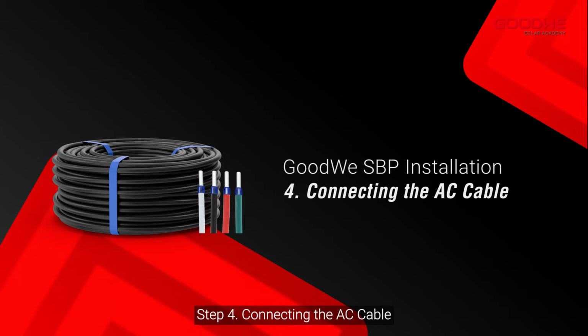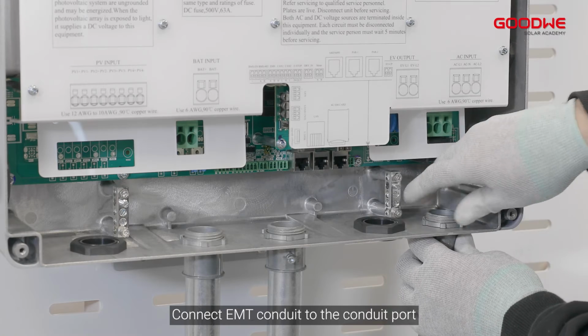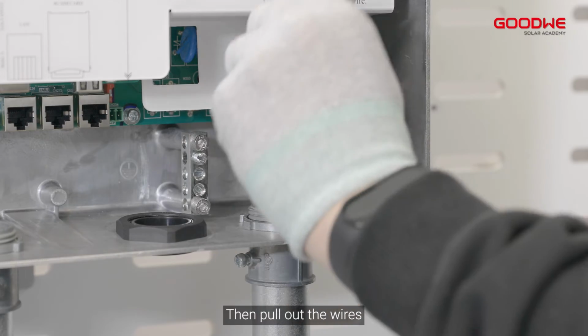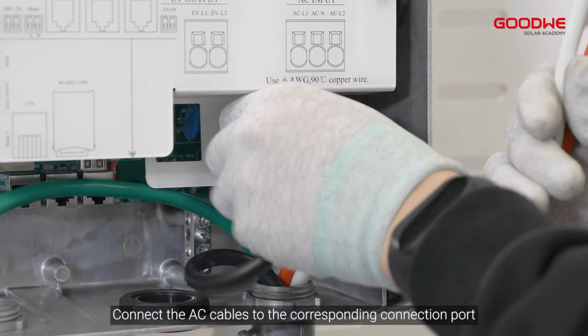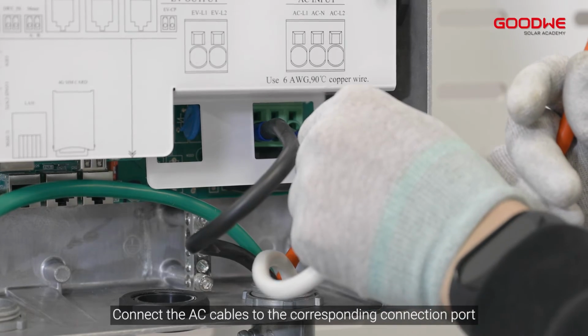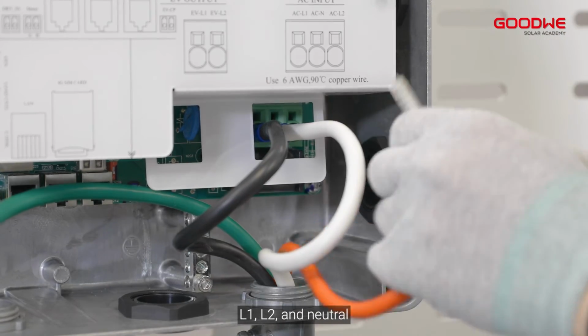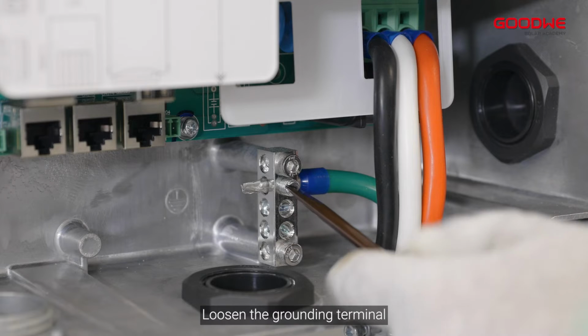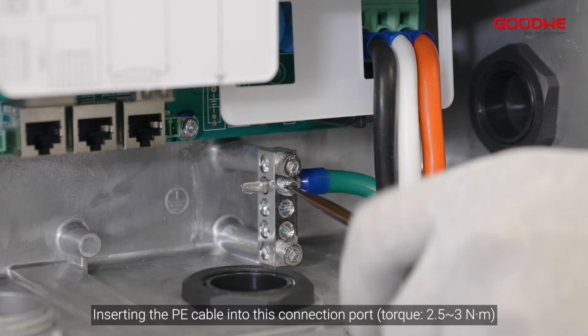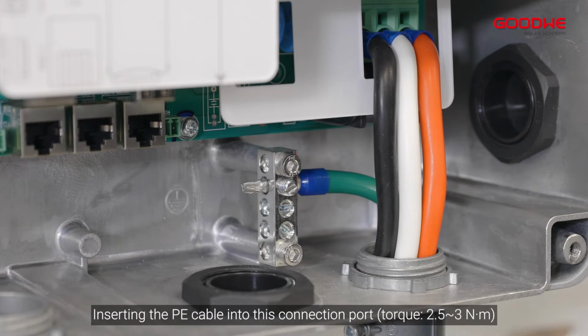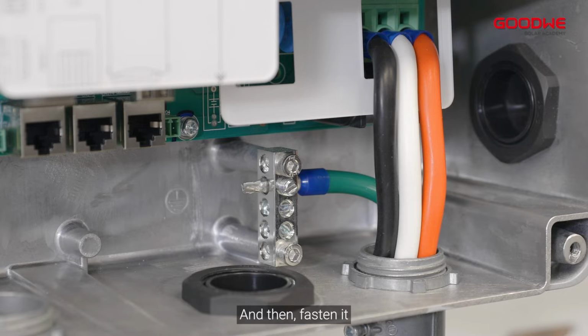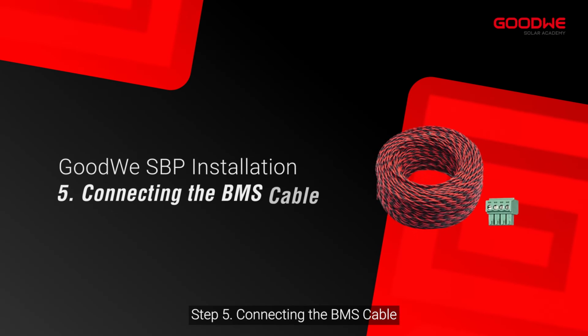Step 4. Connecting the AC cable. Connect EMT conduit to the conduit port. Then pull out the wires. Connect the AC cables to the corresponding connection ports, L1, L2, and neutral. Loosen the grounding terminal, insert the PE cable into this connection port, and then fasten it.